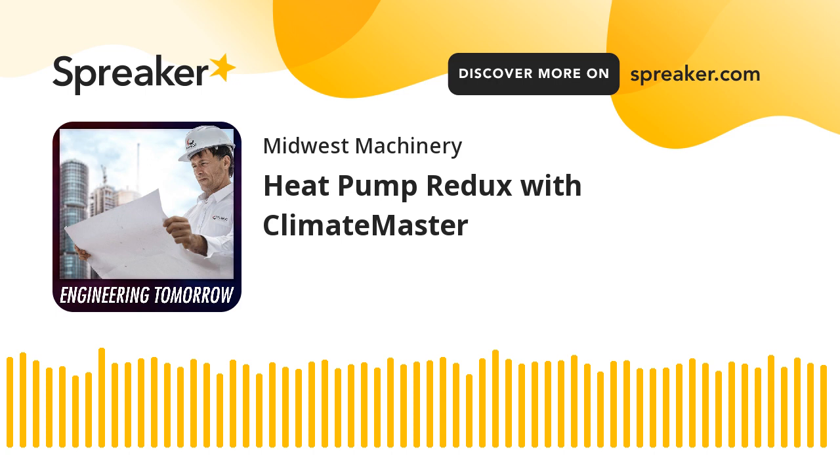In the heating mode, the refrigerant circuit is reversed. The refrigerant to water coil now operates as the unit's evap, and the refrigerant to air coil acts as the unit's condenser.